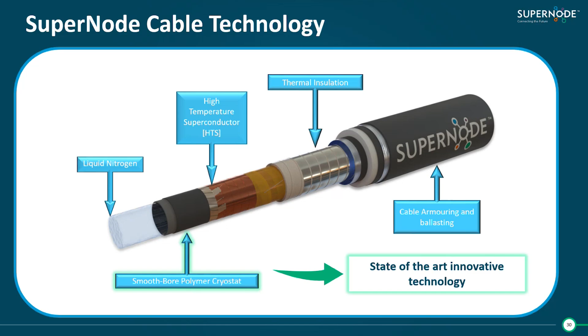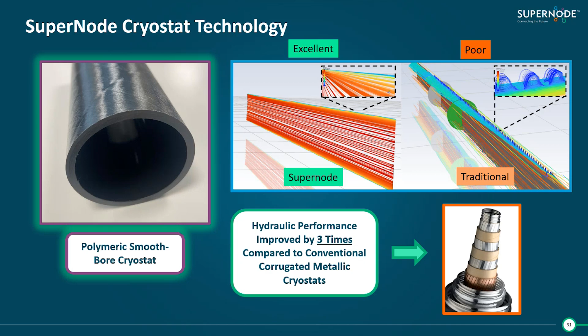So the Supernode cryostat technology itself, where we are better is here. The performance profile in this screen grab from a model output shows quite smooth current flows within the fluid compared to traditional methods which rely on metal cryostats, which have inherent problems that have been an issue for superconducting cables in the past. The smooth bore polymer cryostat delivers this level of functionality, and we can see an order of magnitude of gains in performance from our technology compared to what has previously been available.